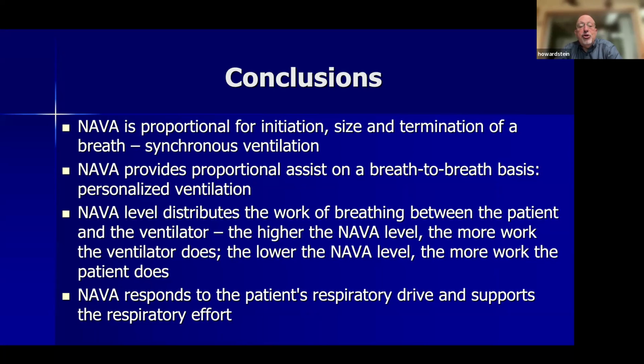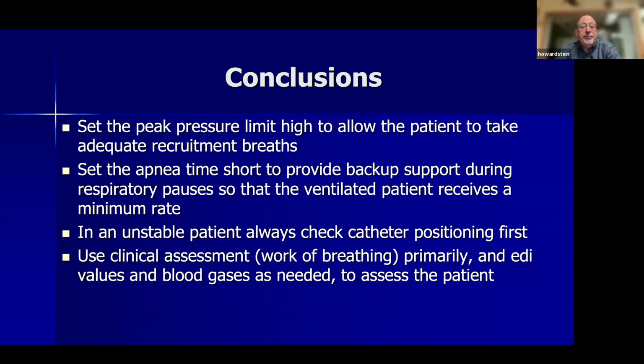The NAVA level distributes the work of breathing between the patient and the ventilator. The higher the NAVA level, the more work the ventilator does. The lower the NAVA level, the more work the patient does. NAVA responds to the patient's respiratory drive and supports the patient's respiratory effort.